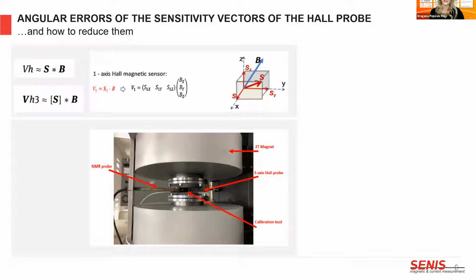First, precise calibration of the Hall probe is performed in our accredited calibration lab. Here we see the setup for this calibration: the magnet, the NMR Tesla meter, and the mechanical tool. The 3-axis Hall probe is positioned into this setup from several different orientations. The Hall output voltages are measured, read, and then substituted into these equations, and the inverse matrix is then stored into the magnetometer's memory.